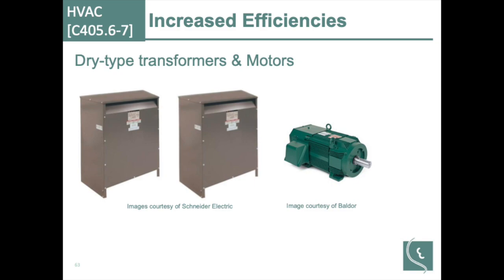Increased efficiency requirements for transformers and motors. For transformers, one thing to be aware of: can you tell the difference between those two? One's a high efficiency, one's a low efficiency. You just got to look at the nameplate on it. Motors, they're moving more towards permanent magnet motors and electronically commutated motors. The technology has improved. Those motors are now available in larger sizes. So again, driving the efficiency improvements from the industry itself.